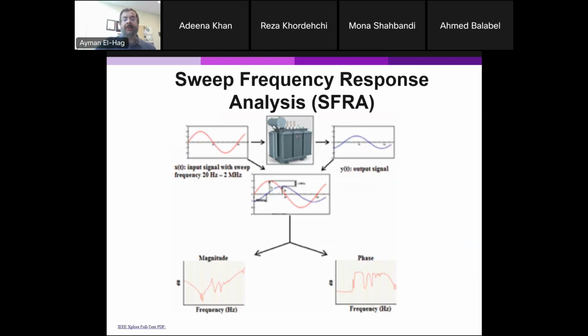The last test I talk about is the SFRA, the sweep frequency response analysis. Again, many of you present that, so I try to present something different. But the test, in a simple way, you apply a variable frequency input signal that goes from 20 hertz to 2 megahertz. Then you measure the response. So maybe you apply to the high voltage and measure the response in the high voltage while keeping the low voltage open or short circuited, or apply to the low voltage, measure in the low voltage, and so on and so forth.